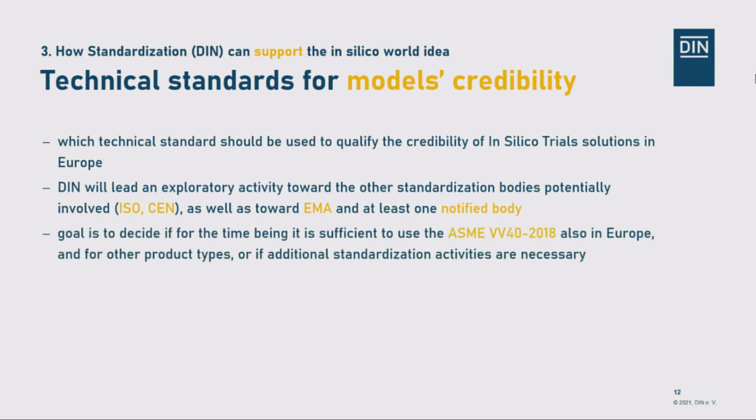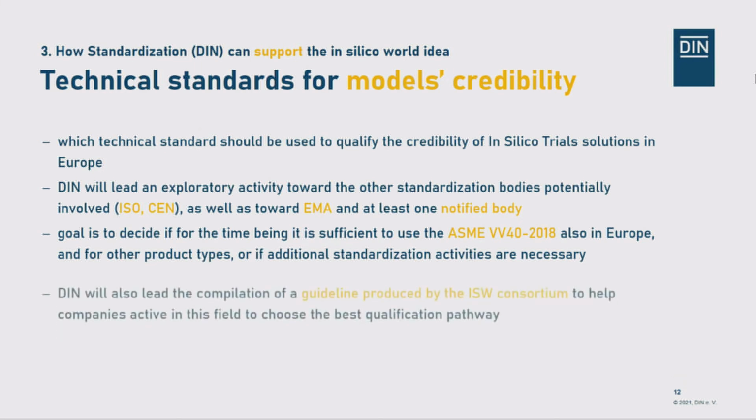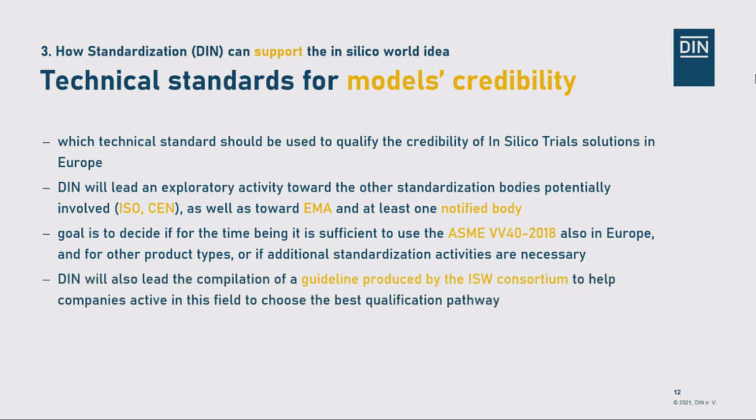I guess most of you are aware of the ASME V&V 40 2018. One point of the work within this project will be to clarify and decide for the time being if it is sufficient to use this American standard also in Europe, or if additional standardization activities are necessary. Furthermore, DIN will also lead the compilation of guidelines that will be produced by the In Silico World Consortium. This guideline is to help companies active in this field to choose the best qualification pathway.